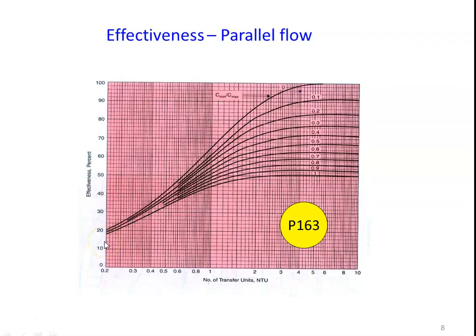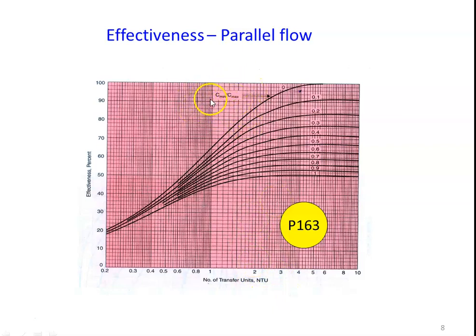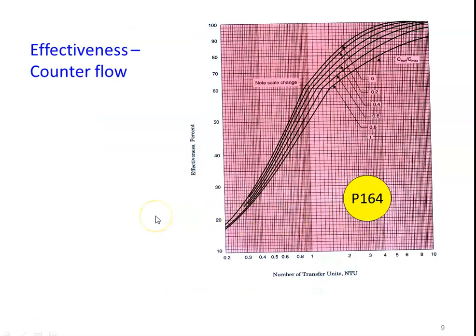To calculate the effectiveness using the NTU chart: NTU is on the x-axis, effectiveness percentage is on the y-axis, and the lines represent different values of C minimum by C maximum. For the rating problem, knowing NTU and the C ratio, find the effectiveness. For the sizing problem, knowing the effectiveness and C ratio, find the NTU. The chart on page 163 is for the parallel flow heat exchanger, and page 164 is for the simple counter flow heat exchanger.